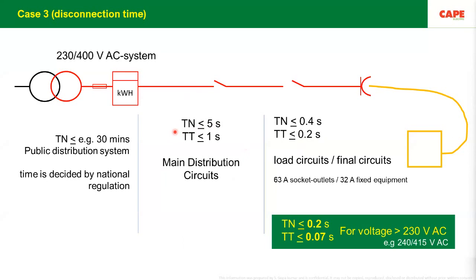But please keep in mind that these times are derived in the standard including protective equipotential bonding. It means all the metallic parts; I have a slide which I will explain later on. So these timings are applicable if you have implemented protective equipotential bonding. If you have not implemented protective equipotential bonding, then the disconnection times, I would say, have to be even lesser. So the third point is the disconnection time of a circuit during a fault.